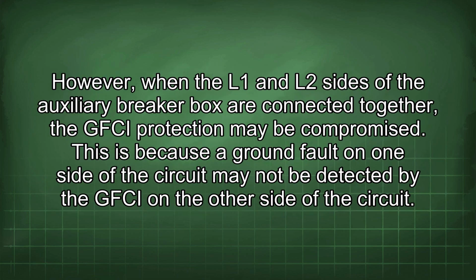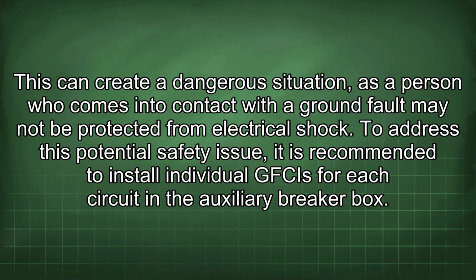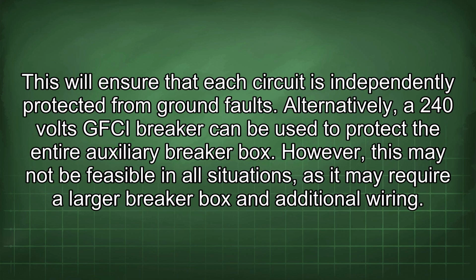However, when the L1 and L2 sides of the auxiliary breaker box are connected together, the GFCI protection may be compromised. This is because a ground fault on one side of the circuit may not be detected by the GFCI on the other side of the circuit. This can create a dangerous situation, as a person who comes into contact with a ground fault may not be protected from electrical shock. To address this potential safety issue, it is recommended to install individual GFCIs for each circuit in the auxiliary breaker box. This will ensure that each circuit is independently protected from ground faults.